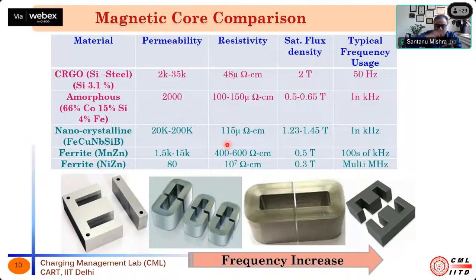In a normal CRGO core we use lamination. Why? Because we want to reduce the eddy current - the resistance is rho L over A, so we want to decrease the value of area so that the resistance is kind of high, so that no eddy current will flow. That's why we laminate the core.